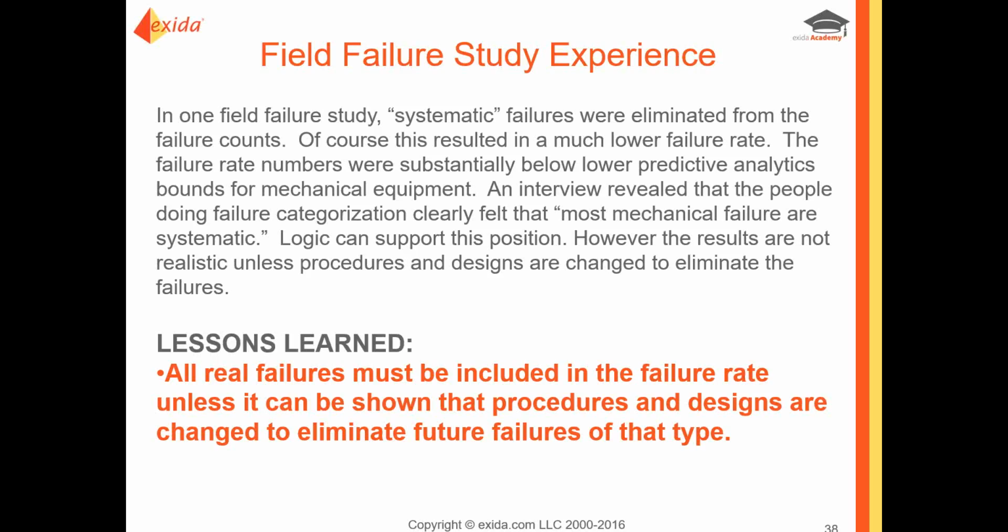However, the results are very unrealistic unless procedures and designs are changed to eliminate future versions of every failure. The bottom line is, all real failures must be included in a data collection system, whether they're, quote, systematic or not, unless it can be proven that procedures and/or designs are changed to eliminate future instances of that failure.